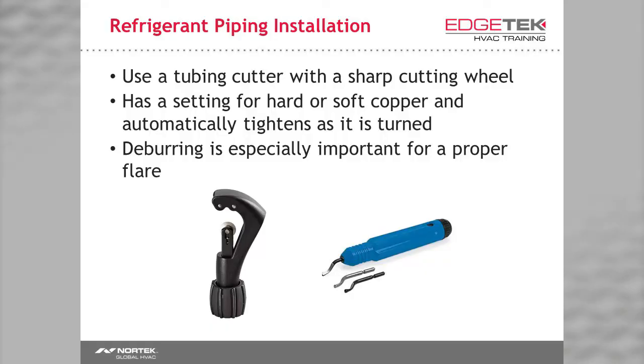To start, you'll want a good tubing cutter with a sharp cutting wheel. The one pictured is from CPS and has a setting for hard or soft copper, and it automatically tightens as it is turned. Don't over-tighten while cutting your copper.